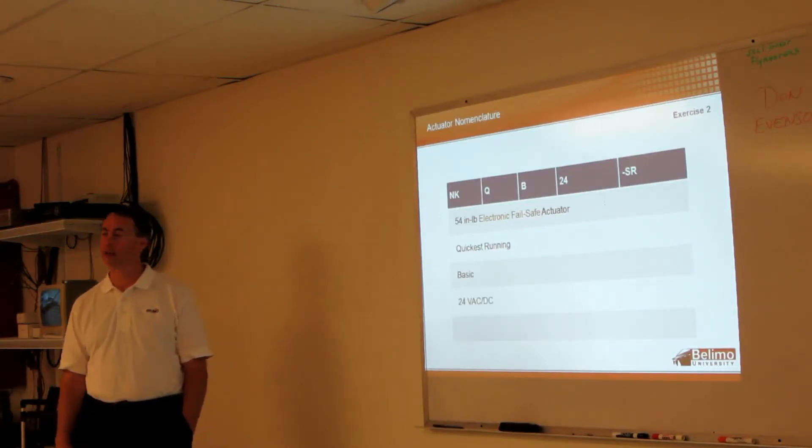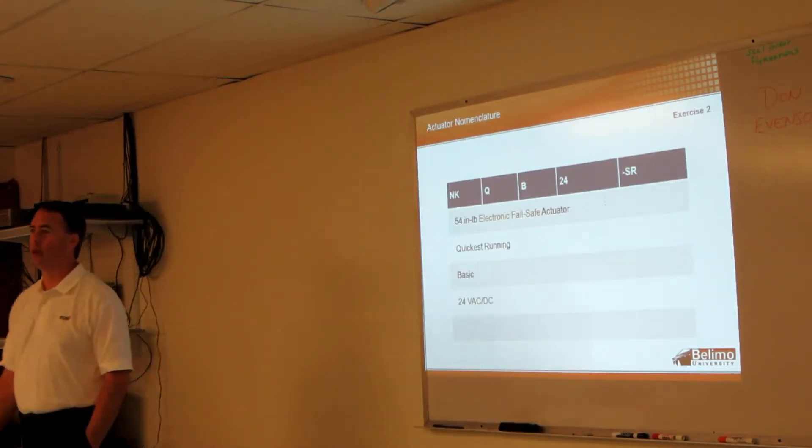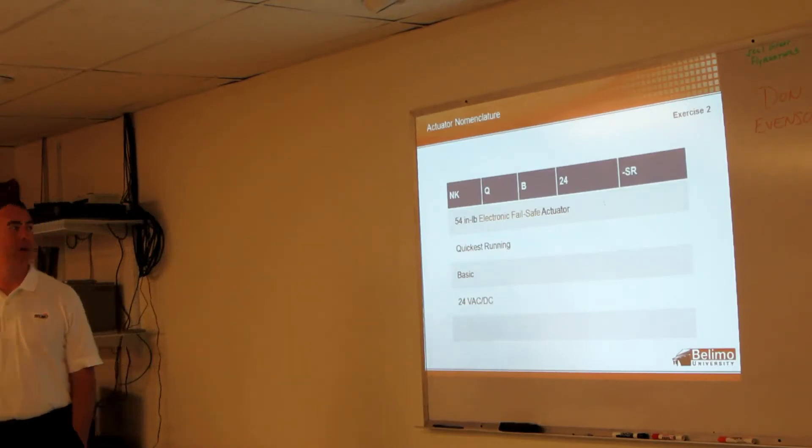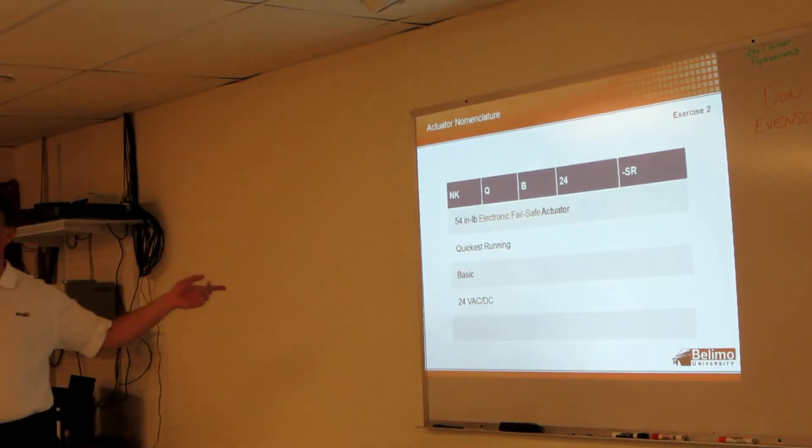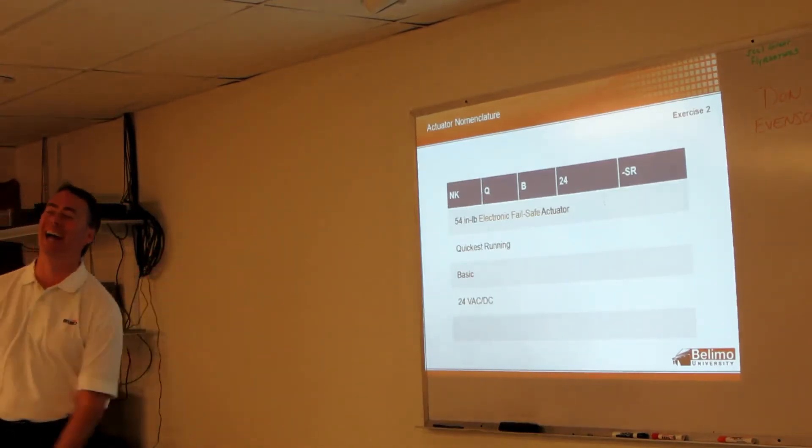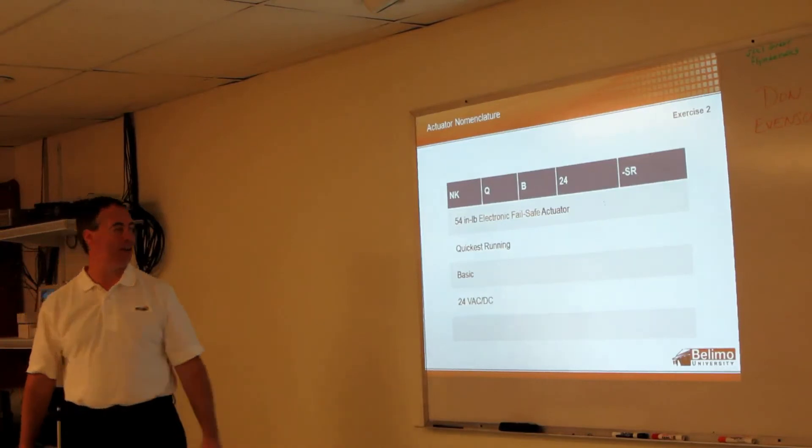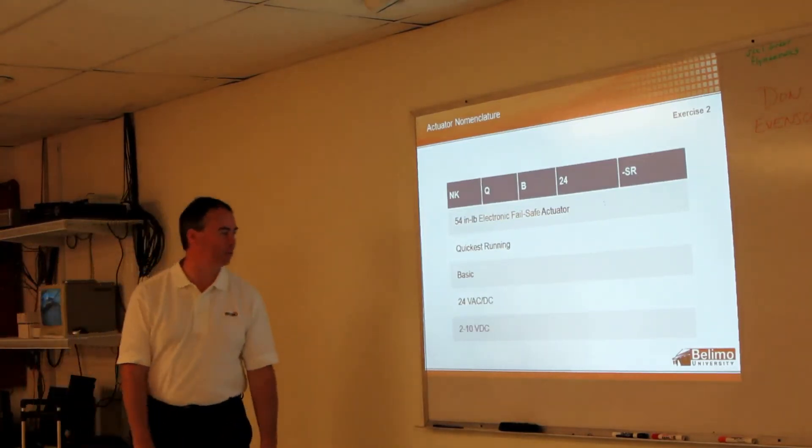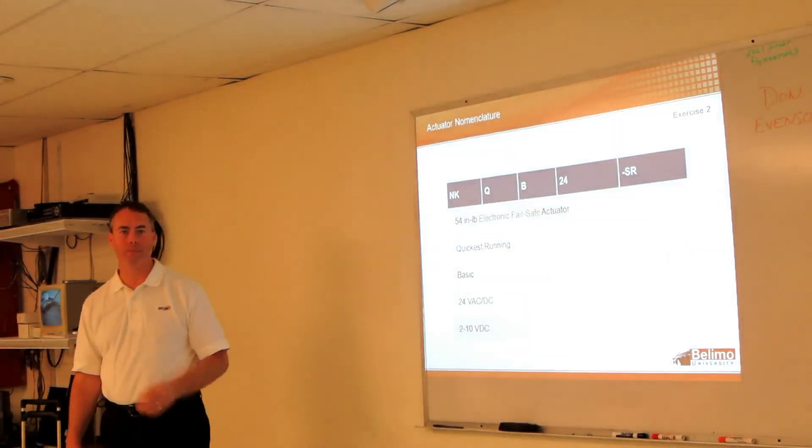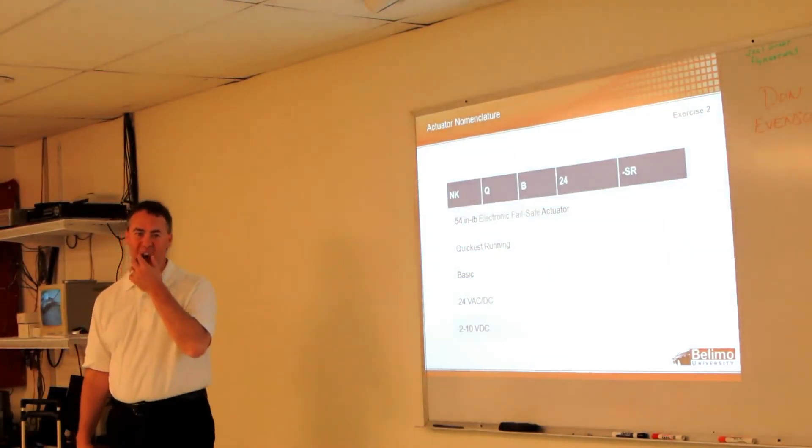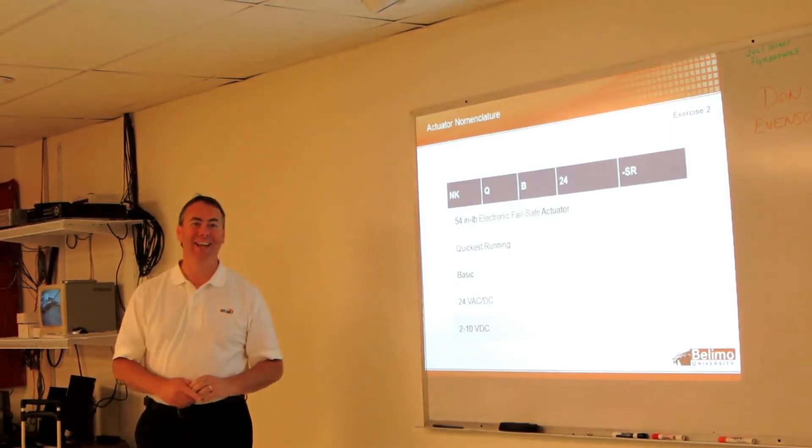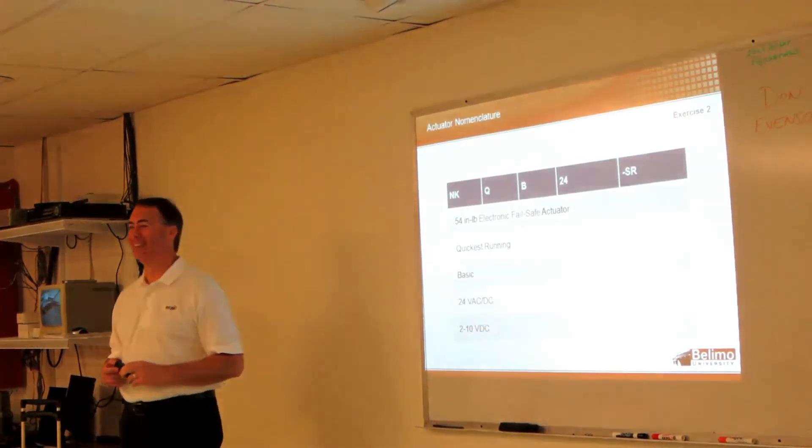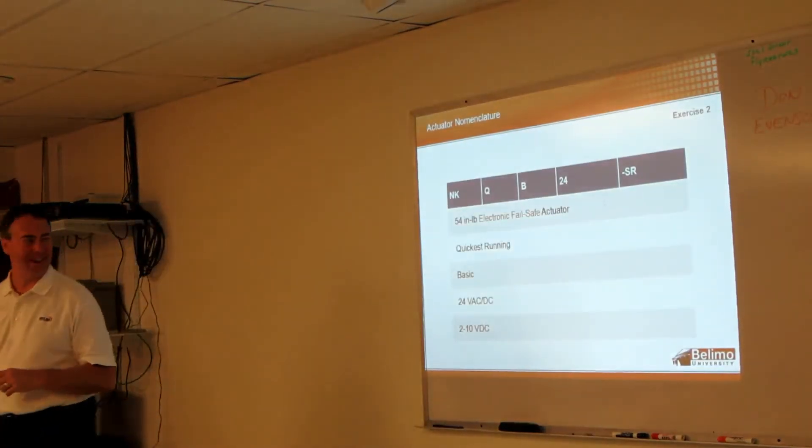Dash SR - not spring return, it's not spring. No, this one's electronic fail-safe. Two to ten modulating, right? Two to ten modulating, yep. Very good. So if you want - if I want you to remember anything out of this entire presentation - it's that SR is not spring return. Exactly.